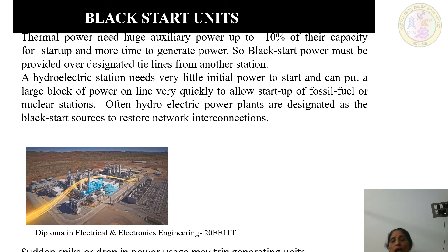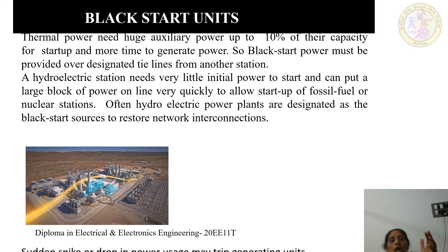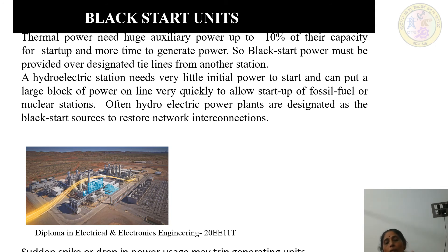Since a hydroelectric power plant is easy to start quickly, it can be used as a blackstart unit for thermal power plants or nuclear power plants. Hydroelectric power plants start fast, and can then be used to bring thermal or nuclear power plants back online as blackstart units.